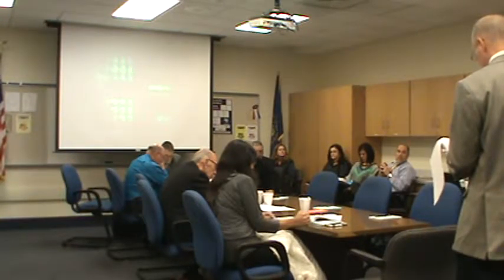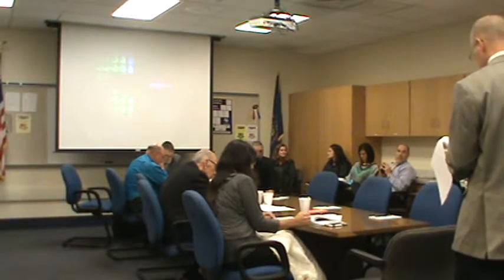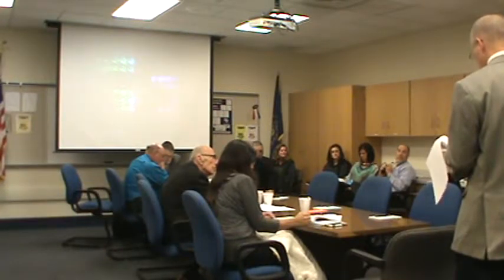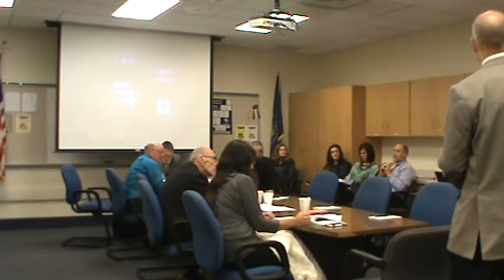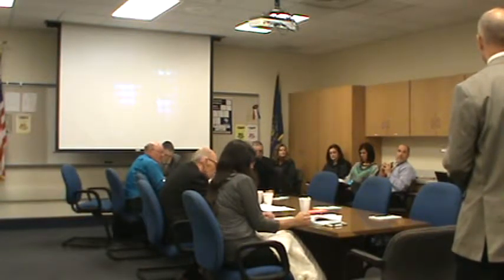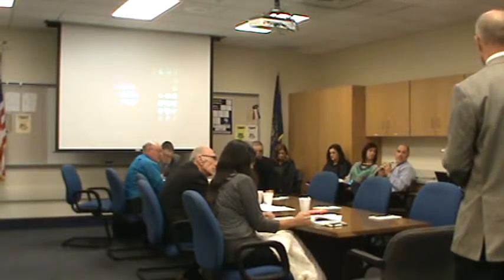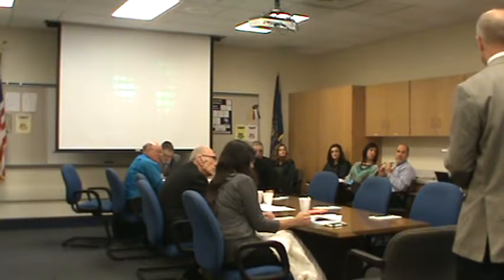The commissioning services is something newer. Jim and I, for probably the last 5 years, have been recommending this. Commissioning is an outside agency that works directly for you, going into the nuts and bolts of the HVAC system to make sure it was installed correctly, the wheels are turning correctly, and the ductwork is doing what it's supposed to do—something that goes above and beyond what we can normally do. We actually climb up into the air handling system, take the air handlers off, and do a detailed reconnaissance of what's been installed to make sure it's working as specified.